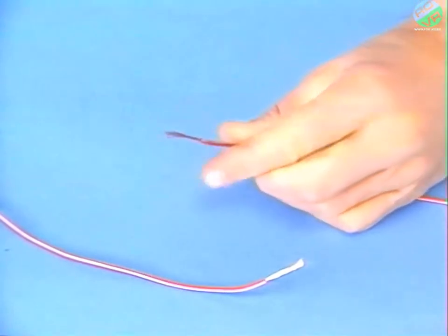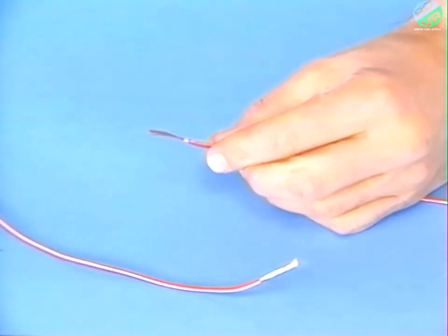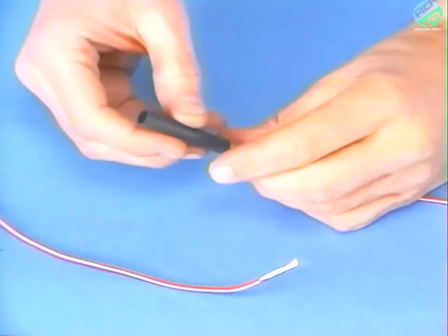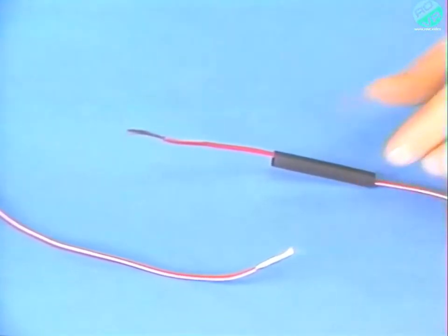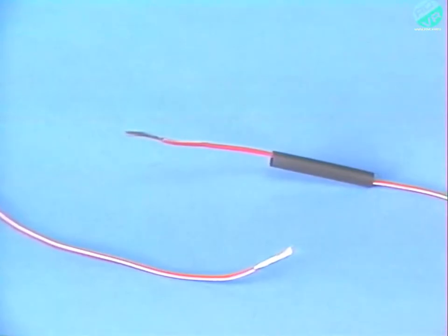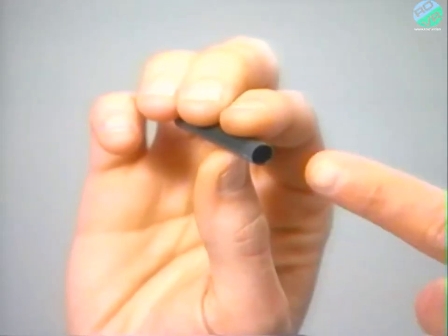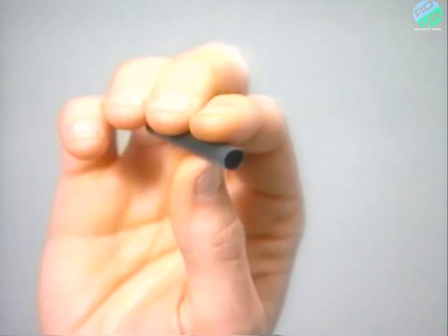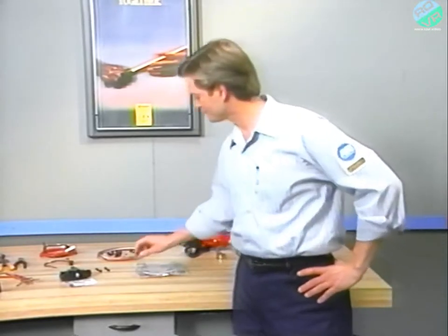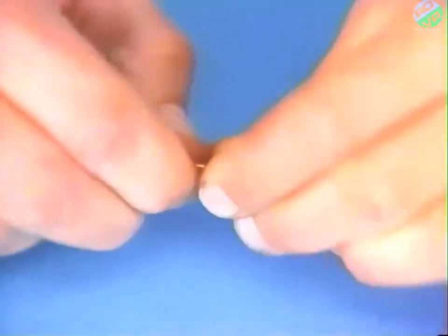When servicing wiring or wiring connectors, you may have to make a soldered connection between two wires. To make a proper splice, start by removing 1 inch of insulation from each of the wires. Place a piece of the proper size heat shrink tubing onto one of the wires. For wire from 10 gauge to 20 gauge, use 1/4 inch shrink tubing. The inside of the shrink tube is coated with a special sealant, which will come out of both ends of the tubing as the shrink tube is heated. Twist the wires together and you're ready to solder.